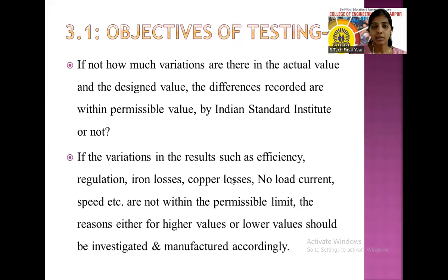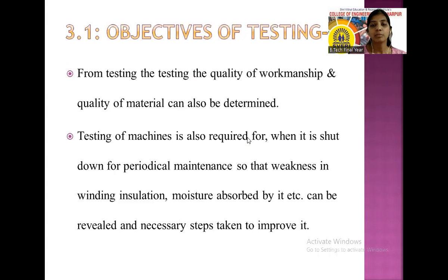So after checking those variations, you have to conduct various tests on the machines to check the efficiency of the machine, then the losses of the machine. There may be iron losses, copper losses, no load current, speed, etc. These points you have to consider, and you have to check the permissible limit of that test, whether the output is falling within the permissible limit or not. If it is falling within the permissible limit, then it is okay. If it is not, then the factors affecting that performance should be checked, and that machine should be restructured once again.